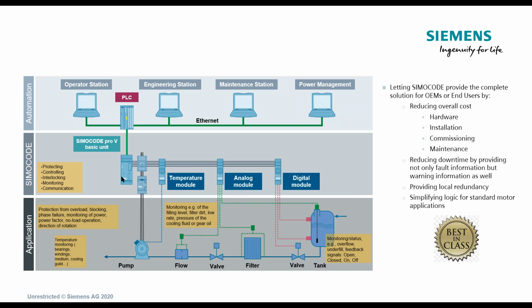Everything's being processed here. This is not an island of automation. It can be if you wanted it to be, but this automation going on here is being reported back to the PLC. But the SIMOCODE itself is running the operations. When maybe it sees a temperature get to a certain point, then it reports back to the PLC and the controller saying, I have a problem, how do you want me to handle it? Or if the analog, if the delta P gets to a certain point, we can just send it up to the operator station and say, hey, we might want to look at this filter. We're getting a delta P across this filter.